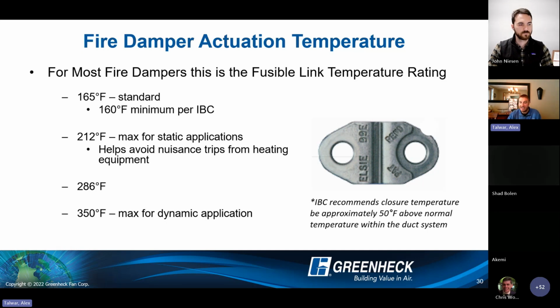Fusible link is the activation or heat response device. You can see the standard temperatures listed here, 165 up to 350. International Building Code does call out a closure temperature, I forget how they actually say it, approximately 50 degrees above the normal temperature within the duct. Well, what does that mean? You don't want your temperature spiking up and having this thing trip. So 50 degrees above whatever the max temperature that it's typically going to see is a good buffer to give it in terms of your melting temperature.